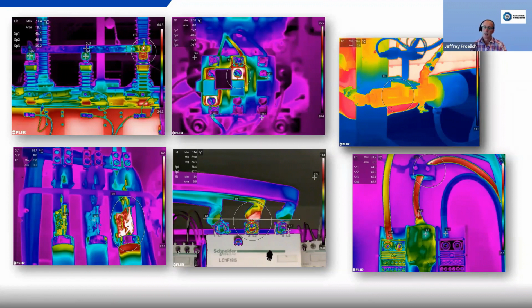On the lower right, you have this circuit disconnect and connection blocks. You've got something on the left, A phase, and you also have a splice and a cable that's starting to deteriorate. I believe this one had exterior insulation breakdown, and so you see a spike where the circle is. But these are really great findings that come to you very quickly and readily, that you wouldn't know of just by visually looking at it, unless you noticed there were deteriorated conditions. You certainly won't know what the temperature is, though.